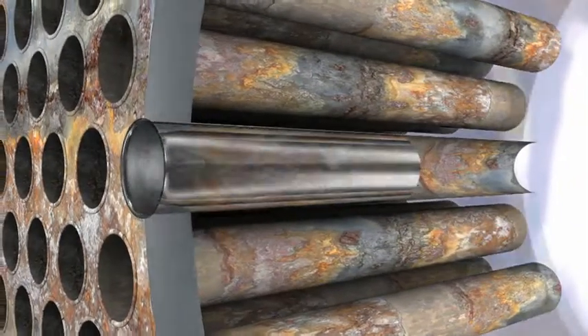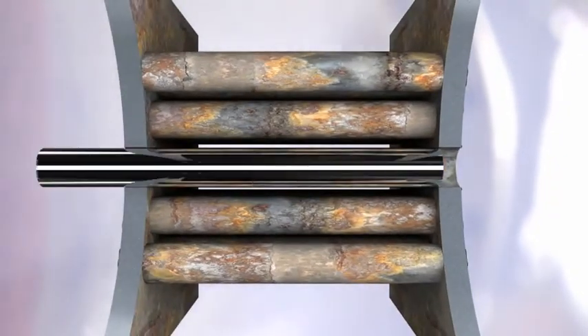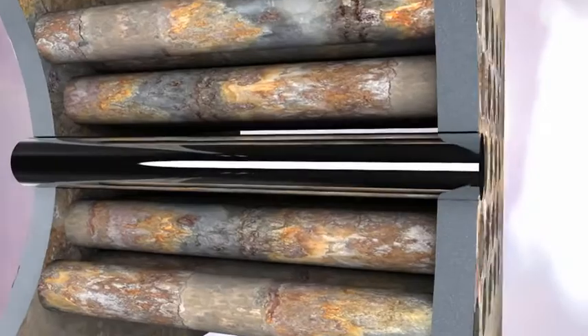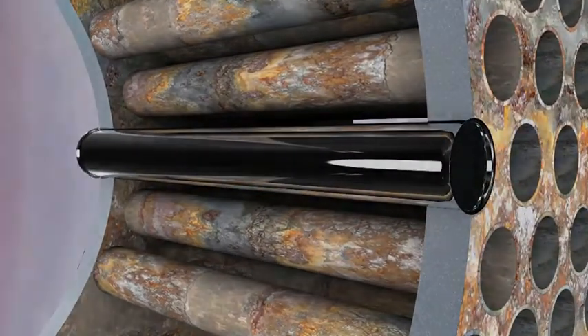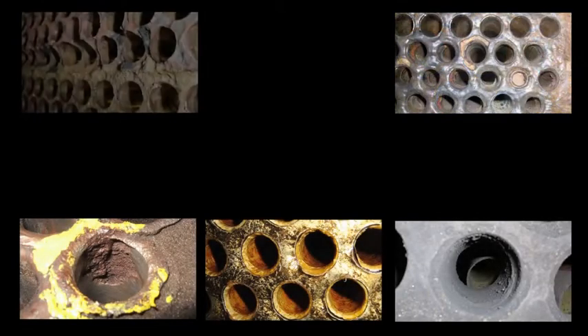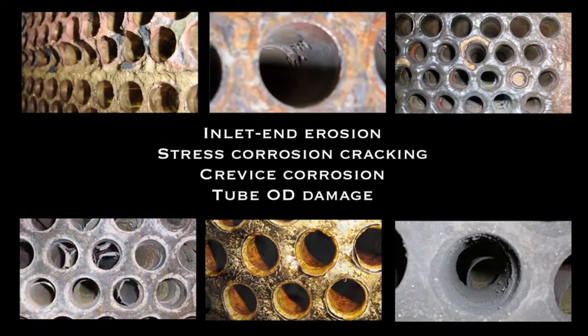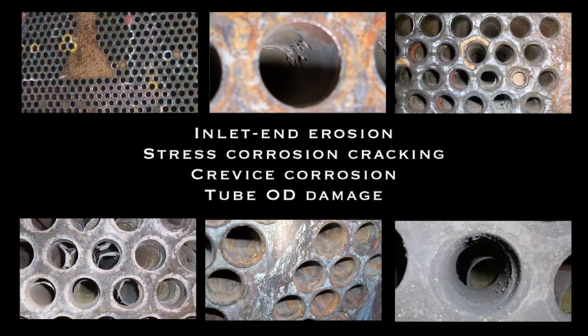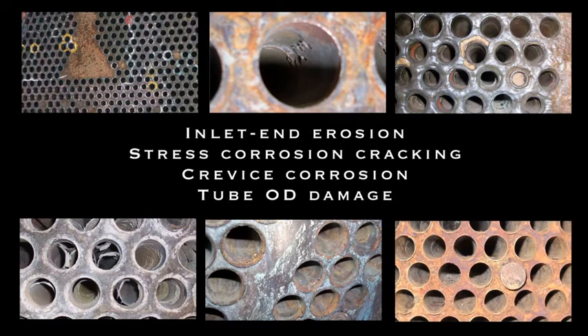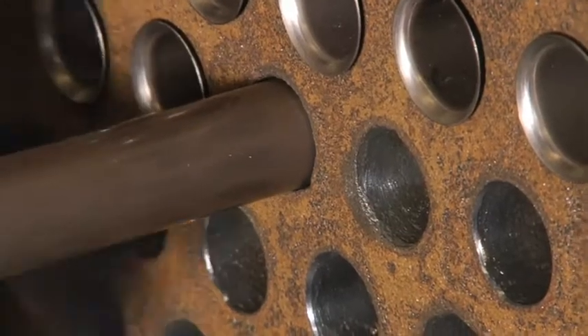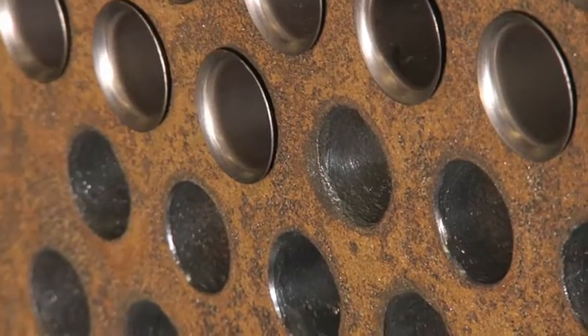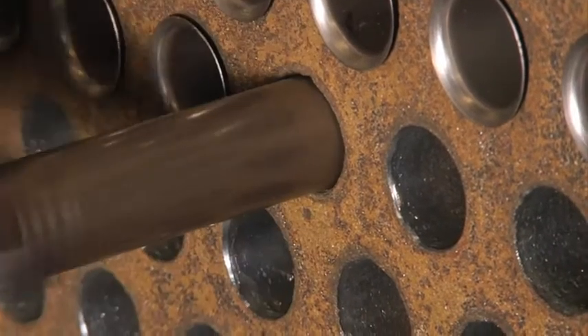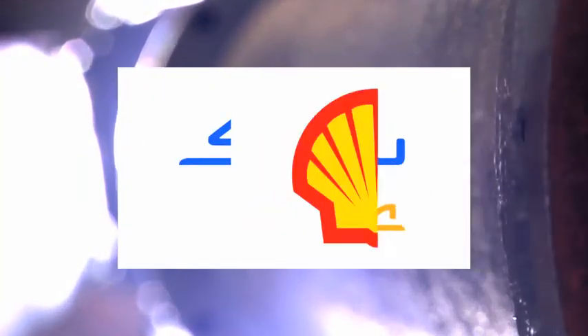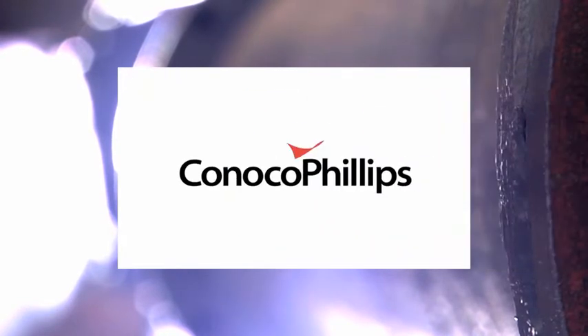Years later, CTI developed and introduced the CTI full-length tube liner, intended for those units suffering damage throughout the length of the tubes. Tube end erosion corrosion is the most common cause of tube failure and includes problems such as inlet end erosion, stress corrosion cracking, crevice corrosion, and tube OD damage. CTI shields repair these failures and eliminate the need for replacing the entire tube, fixing the problem where the damage occurs. Besides the obvious huge money savings on material, there is the reduced labor, equipment, and costs associated with downtime.